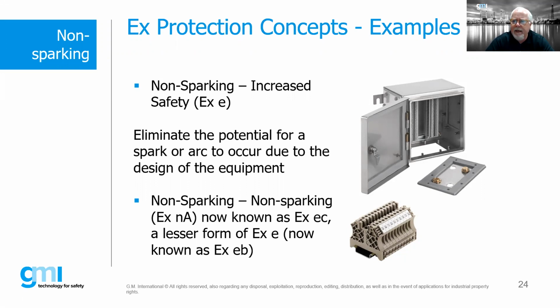We find a lot of Ex e switches, or Ex d switches that have increased safety terminals, or we can find power supplies and relays in which the terminal blocks have sufficient spacing to not allow arcing and sparking. There is a lesser form of this, called Ex nA, which has now been changed to what is called Ex ec. And that is the same concept. So we're basically removing any arcing or sparking from the hazardous environment.